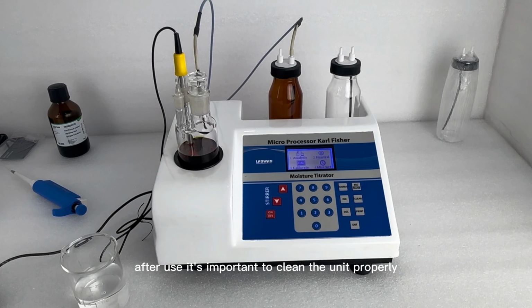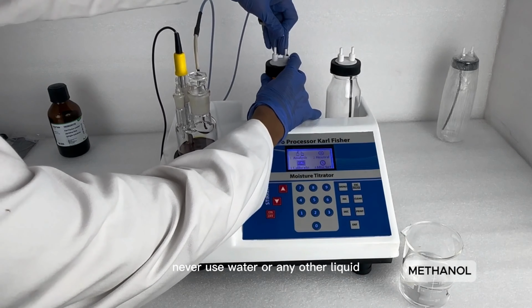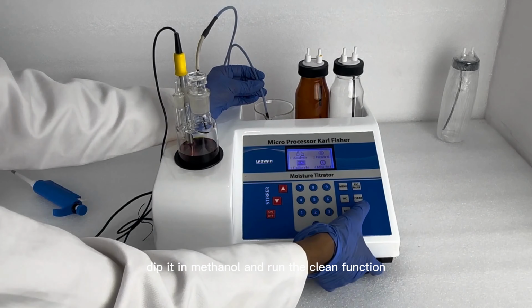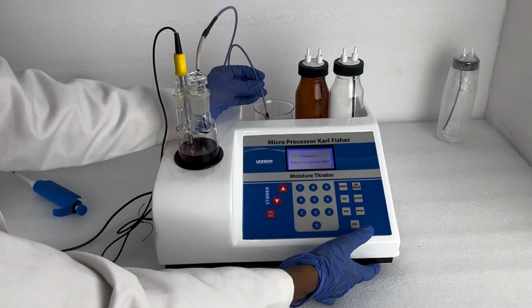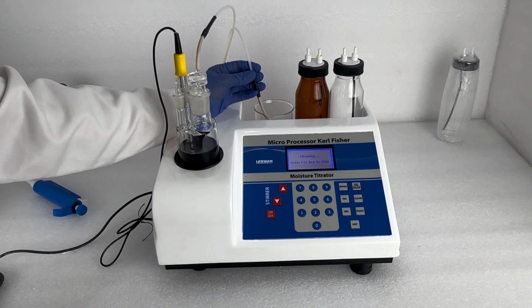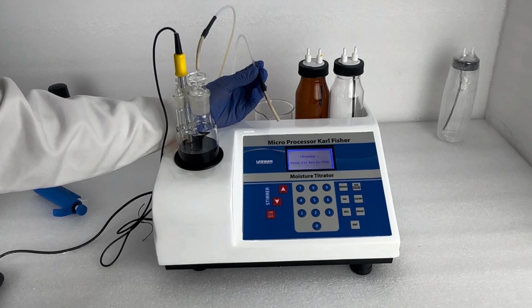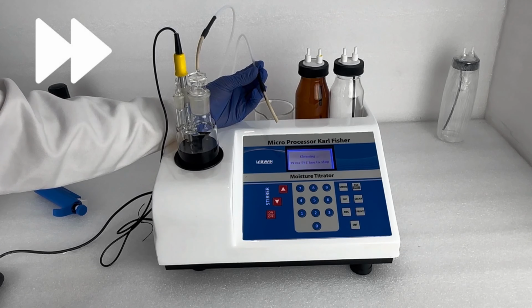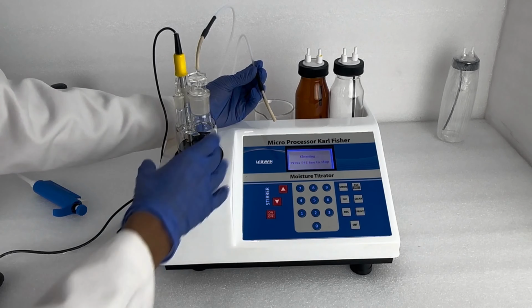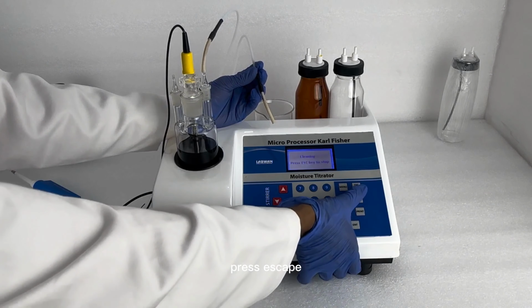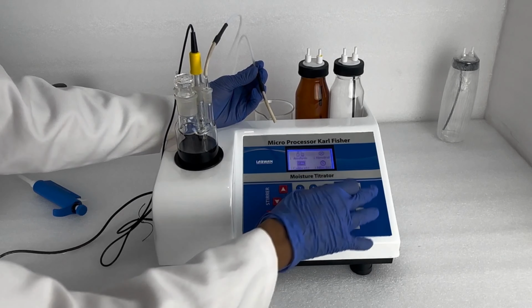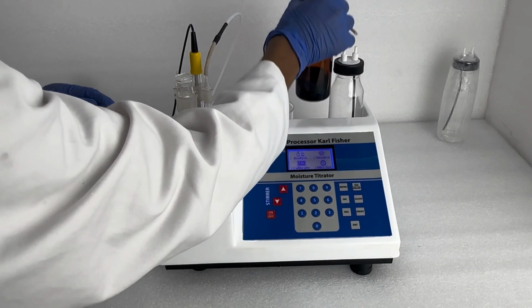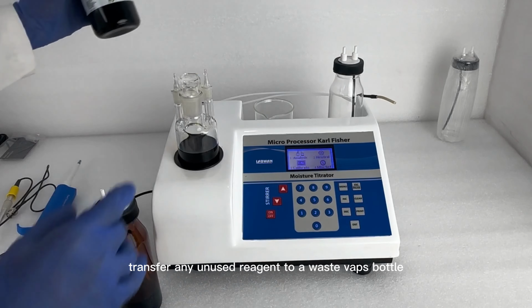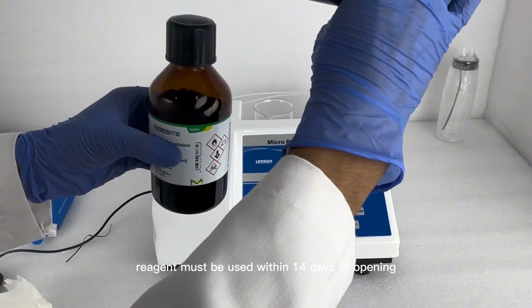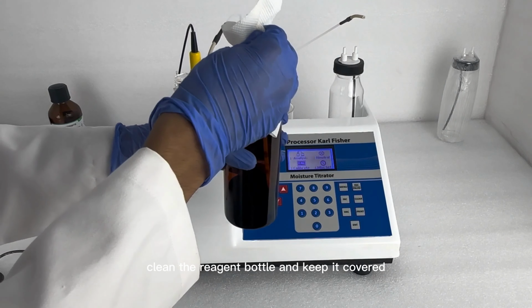After use, it's important to clean the unit properly. Always clean with methanol, never use water or any other liquid. Remove the pipe, dip it in methanol, and run the clean function. Once the methanol has flushed the pipe and nozzle, press escape. Transfer any unused reagent to a waste bottle. Reagent must be used within 14 days of opening. Clean the reagent bottle and keep it covered.